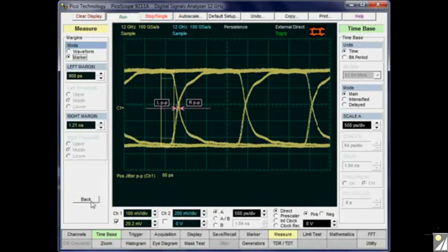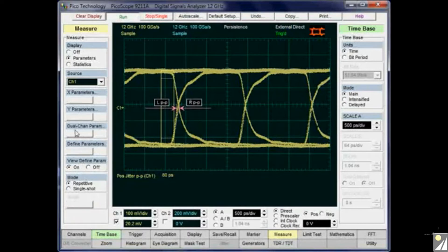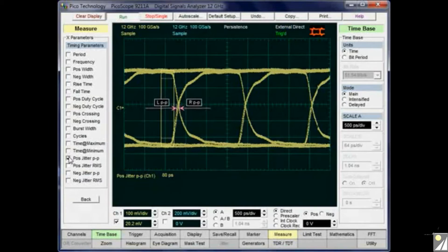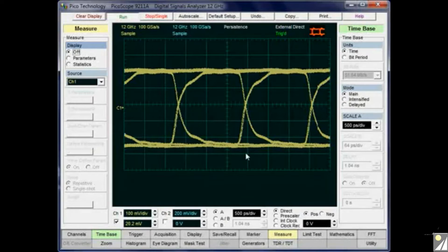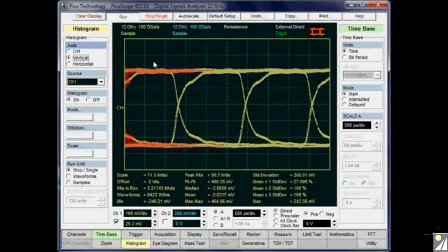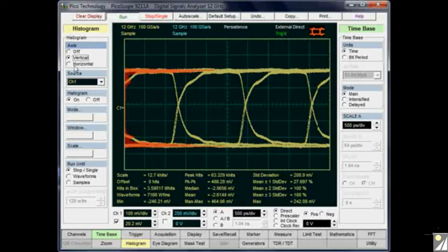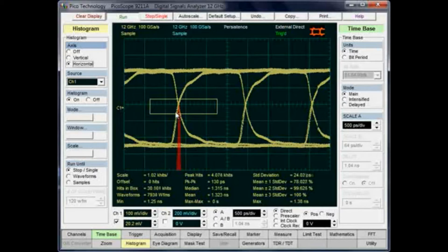The third method is to use histograms. We go to the histogram menu — there are vertical measurements available if you want to measure amplitude noise and variation in signal amplitude, but here we're going to measure horizontal to measure time.